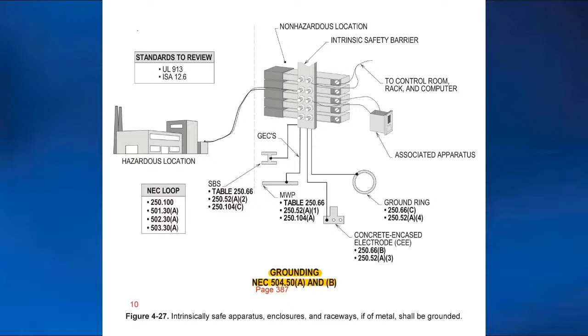Now, if you look, and you grounding guys out there know this, at 250.66, it basically tells you that table 250.66 is only used to size your grounding electrode conductor per code. If you connect it to the structural steel or a metal water pipe, that classifies as an electrode per 250.52. Then you'd go 250.66 A, B, and C, as you guys know.